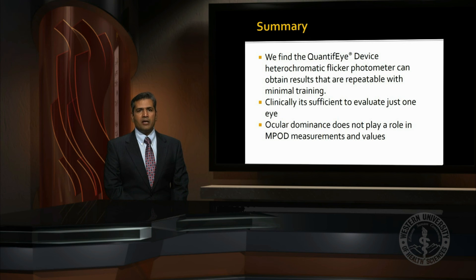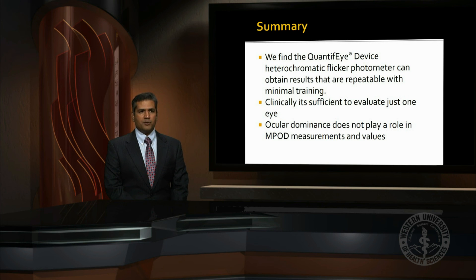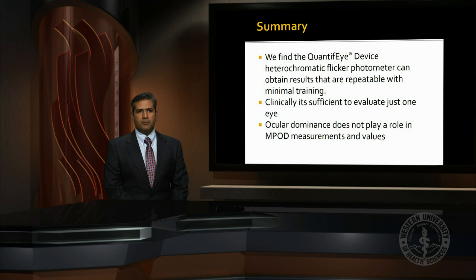In summary, we find the heterochromatic flicker photometer that we evaluated can produce repeatable results with minimal training of subjects. Clinically, it is sufficient to perform the test on just one eye, and ocular dominance does not play a role in the MPOD measurements or its values.